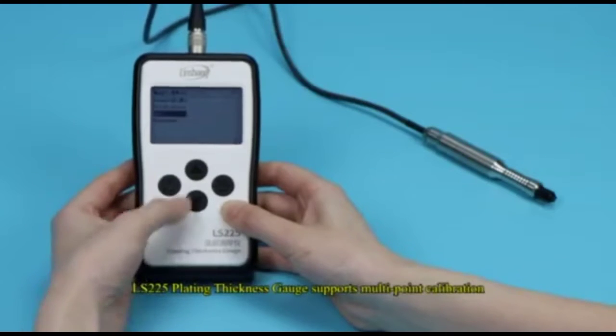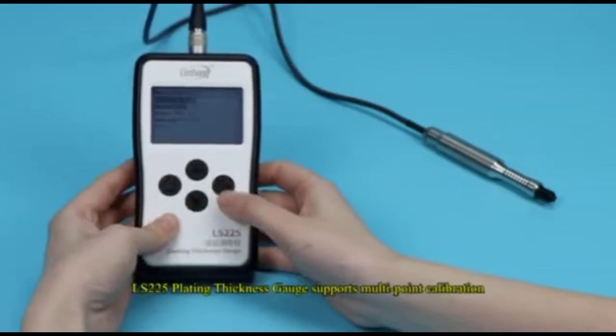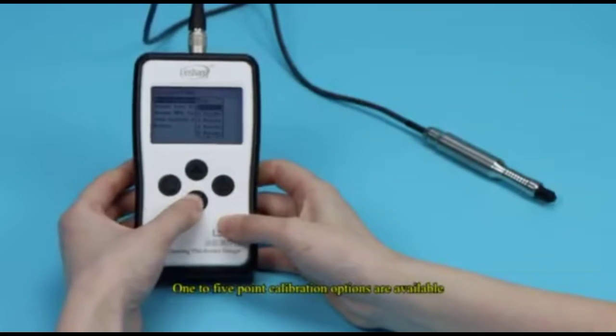LS-225 plating thickness gauge supports multipoint calibration. One to five point calibration options are available.